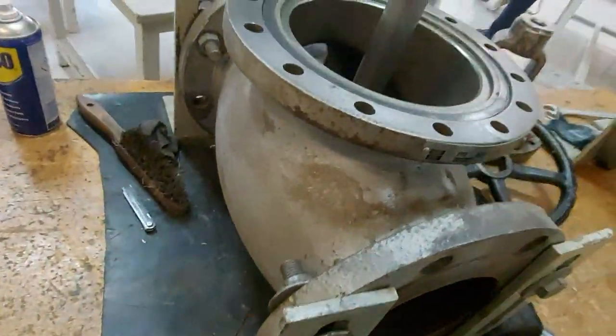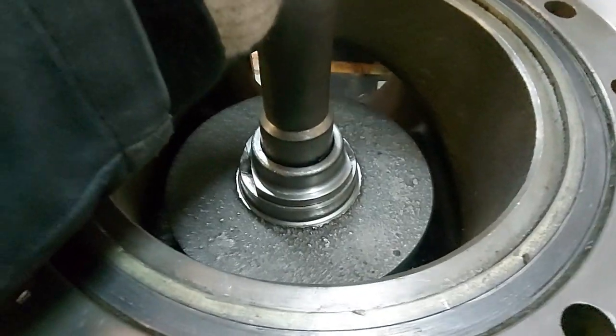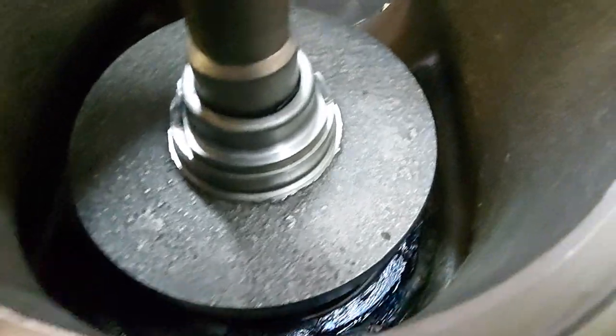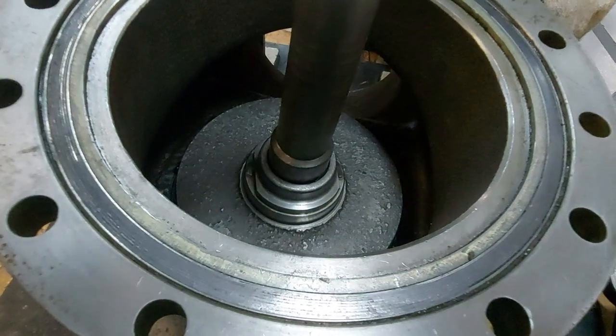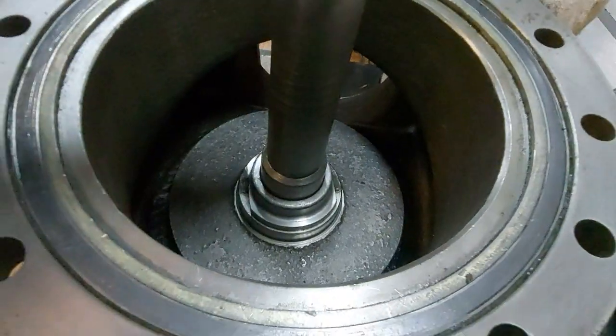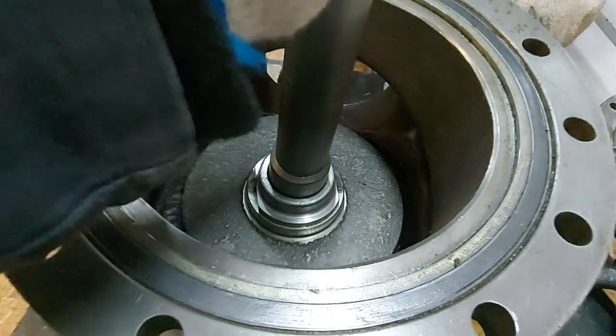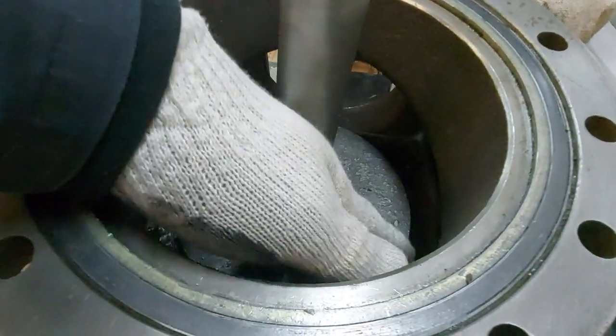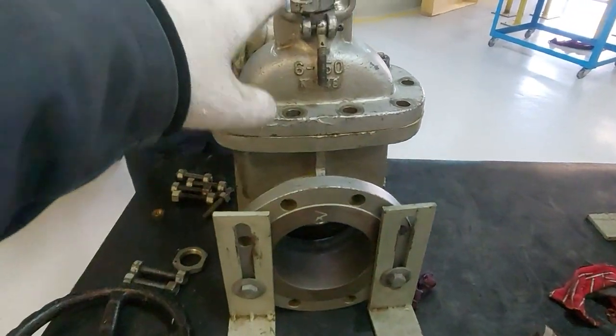For a globe valve, there is no need to assemble the bonnet. You can bring the disc, apply the Prussian blue on the seat below, keep the disc, and put a shim in between so the disc does not rotate alone. When you put the shim in between, it will take the disc with it. If you rotate the stem, the disc also rotates — that is how you get the impressions to know if it is touching the seat.